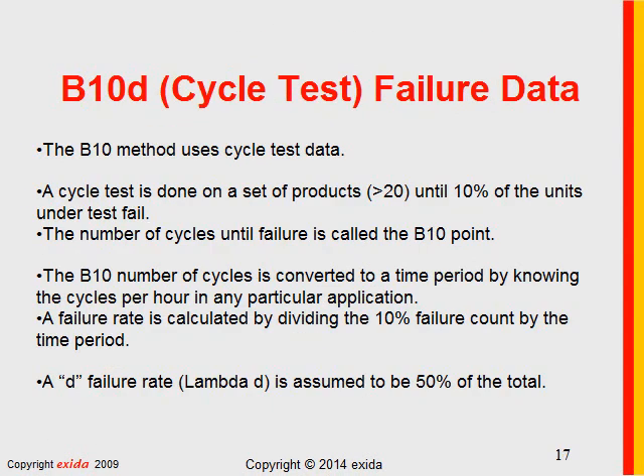The B10 method uses cycle testing. A cycle test is done on a set of products — most useful for mechanical or electromechanical products — cycling them on and off as fast as possible. Given a set of products, typically more than 20, you run the test until 10% fail. The number of cycles until failure is called the B10 point. You convert cycles to a time period by knowing cycles per hour in a particular application and calculate a failure rate accordingly.